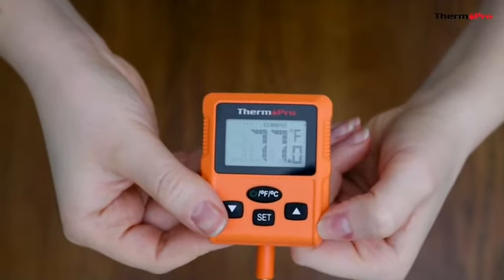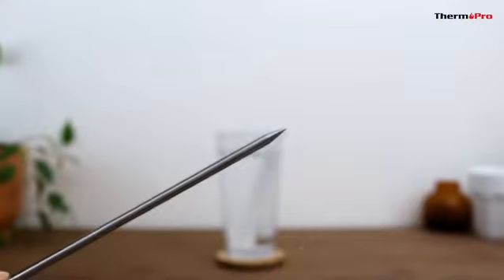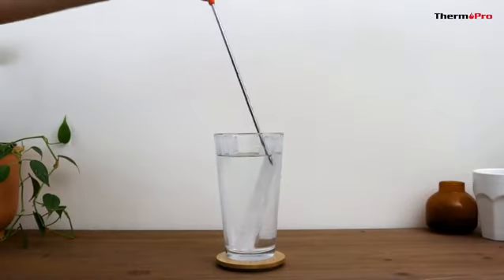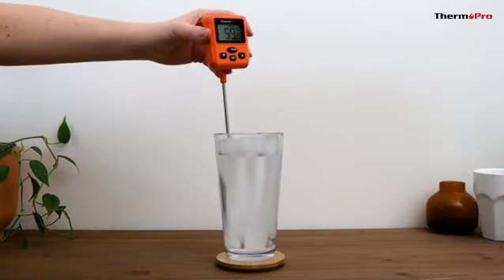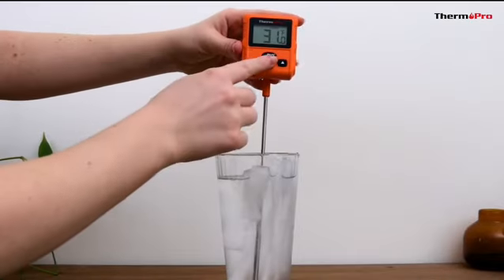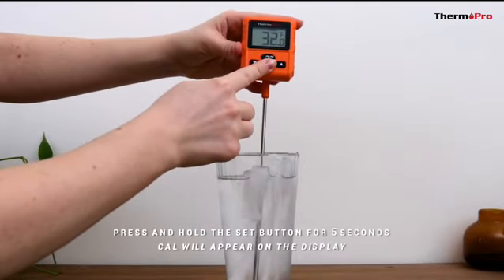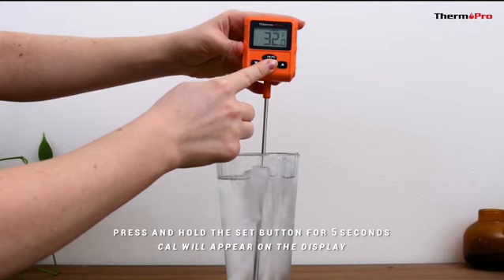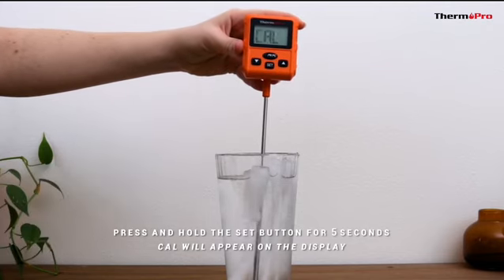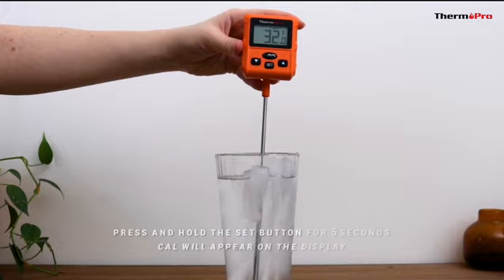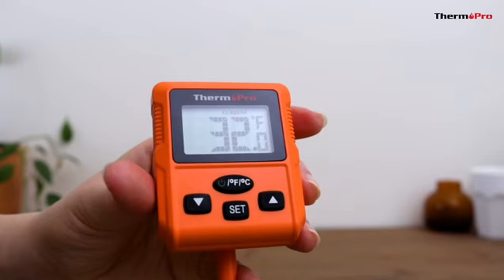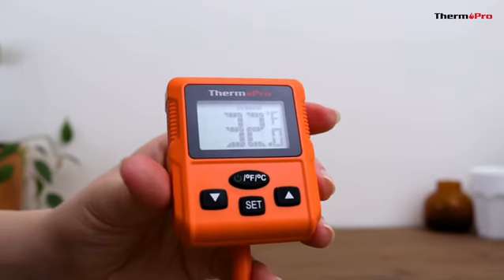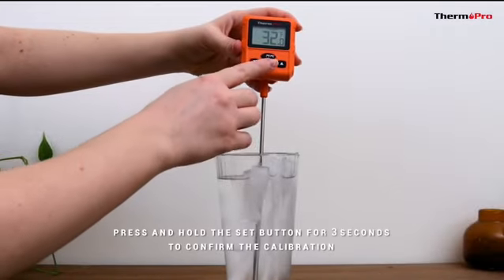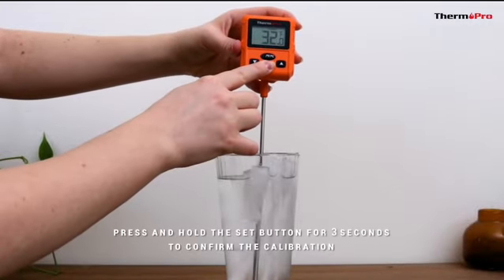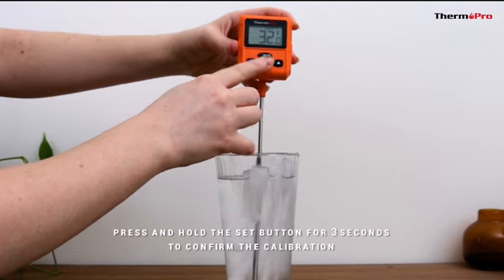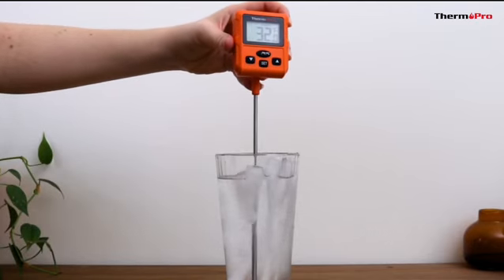Now let's go over the calibration feature. Fill a cup with 70% ice cubes and top it off with cold water, and let it rest for a few minutes. Press and hold the set button for 5 seconds to enter the calibration mode. Cal will appear on the display. Wait until it reaches the lowest value, which should be around 32 degrees Fahrenheit. Then press and hold the set button for 3 seconds to confirm the calibration and exit the calibration mode.